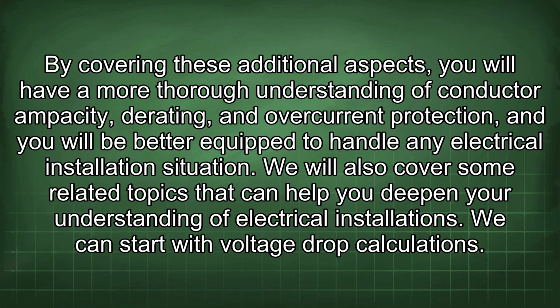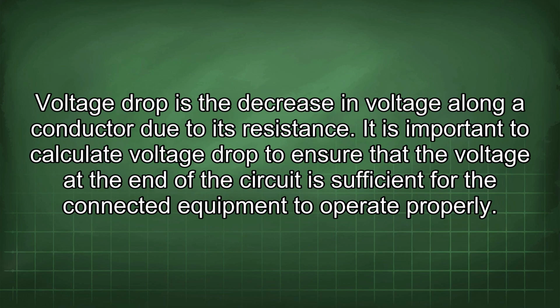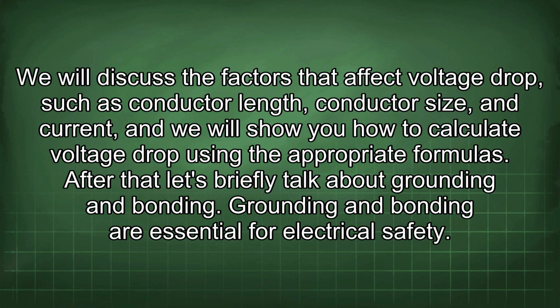We can start with voltage drop calculation. Voltage drop is the decrease in voltage along a conductor due to its resistance. It is important to calculate voltage drop to ensure that the voltage at the end of the circuit is sufficient for the connected equipment to operate properly. We will discuss the factors that affect voltage drop, such as conductor length, conductor size, and current, and we will show you how to calculate voltage drop using the appropriate formulas.